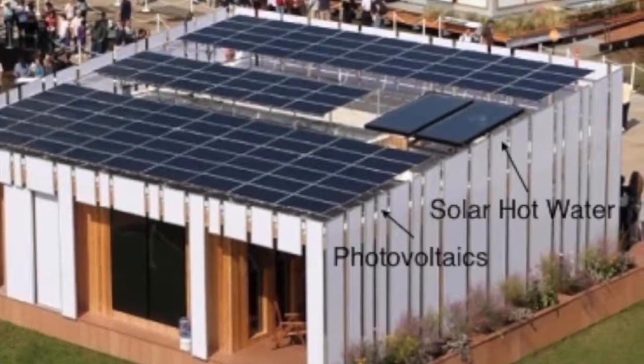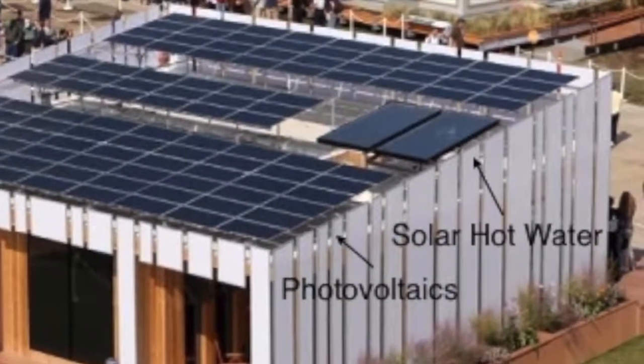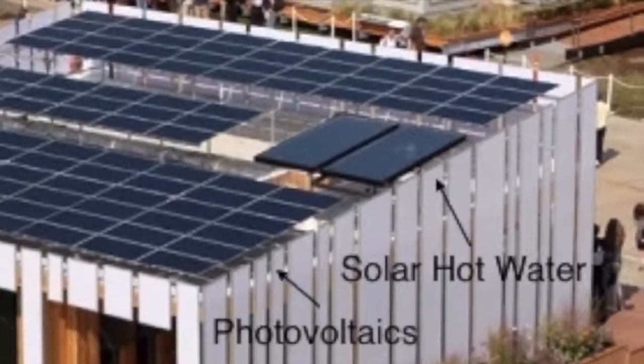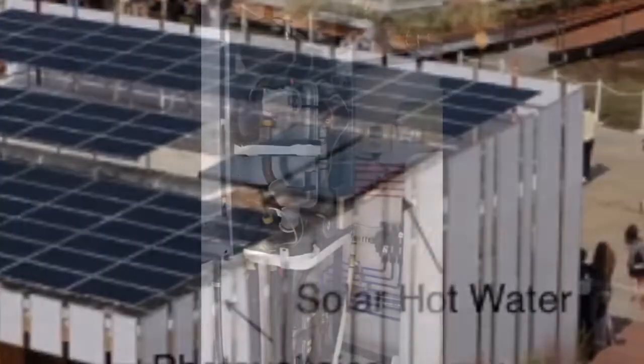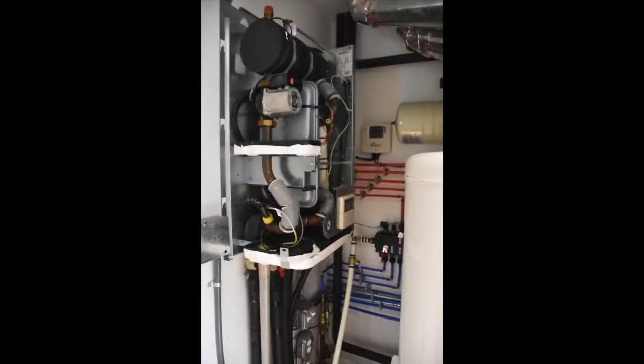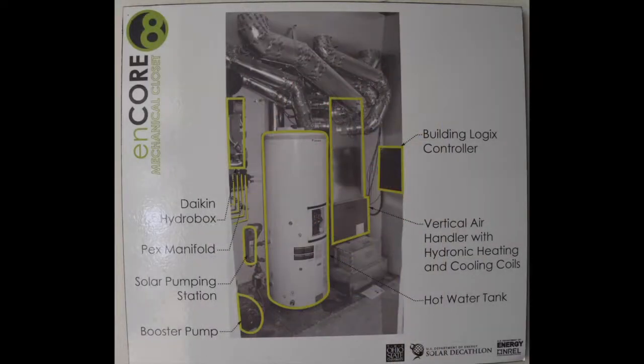Lastly, we have the solar thermal hot water system, which is also located on the roof. The primary method of water heating for the home is the house's indoor heat pump. The solar thermal hot water unit helps to heat the water to reduce the energy demand for this indoor heat pump. To do so, water is circulated in a closed-loop system between the home's hot water tank and the flat-plate solar collectors on the roof. This solar thermal hot water system is integrated into the heat pump controls and can reduce the water heating load by as much as 50 to 70% each year.